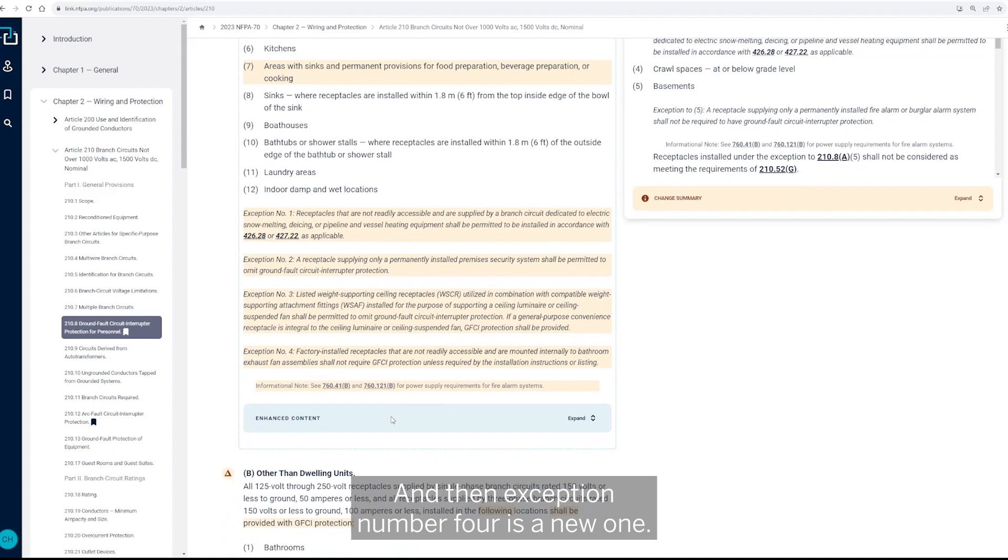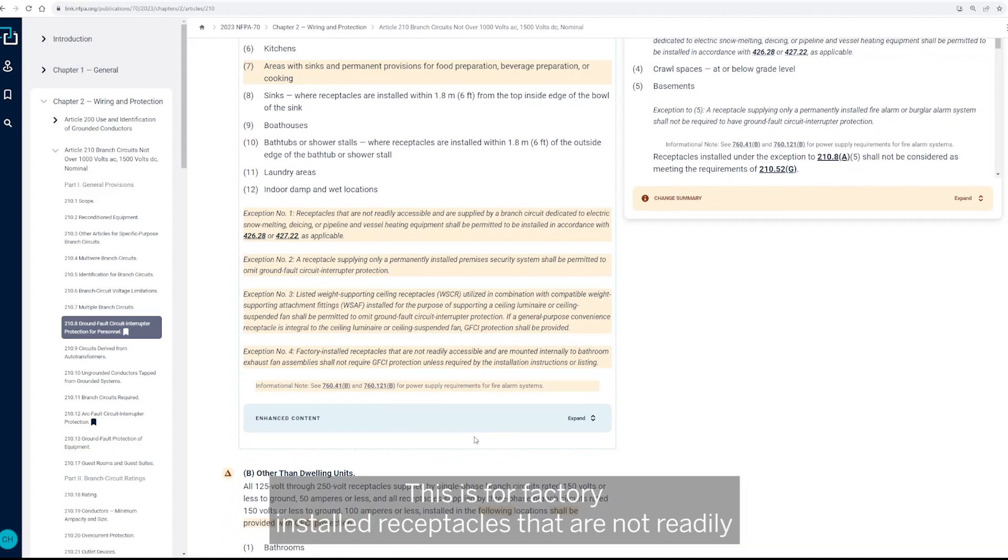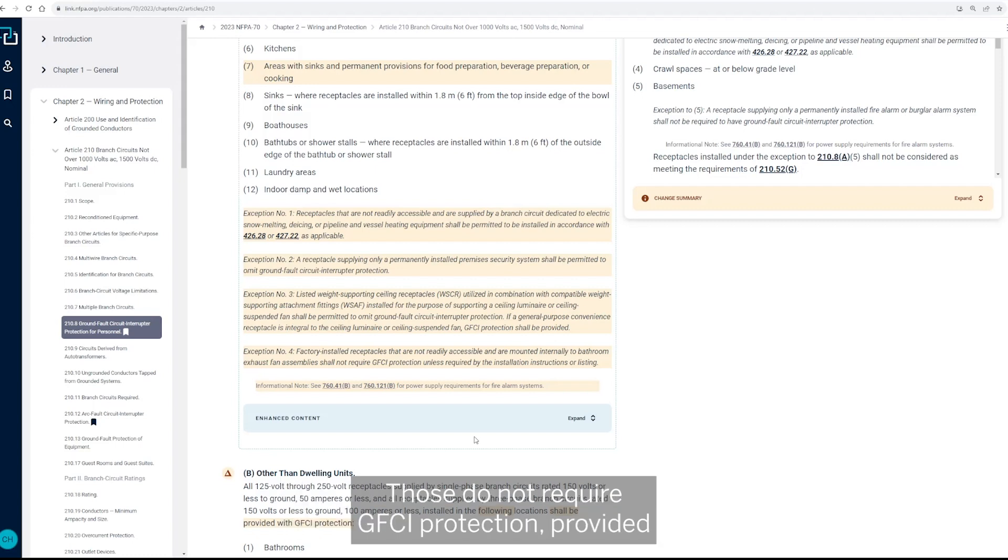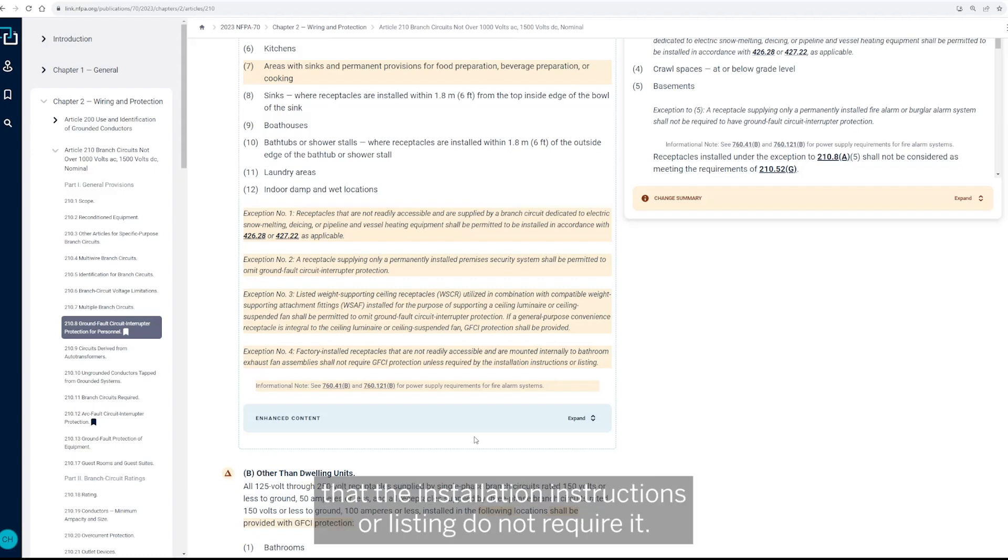And then exception number four is a new one. So this is for factory installed receptacles that are not readily accessible and are mounted internally to bathroom exhaust fan assemblies. Those do not require GFCI protection, provided that the installation instructions or listing do not require it.